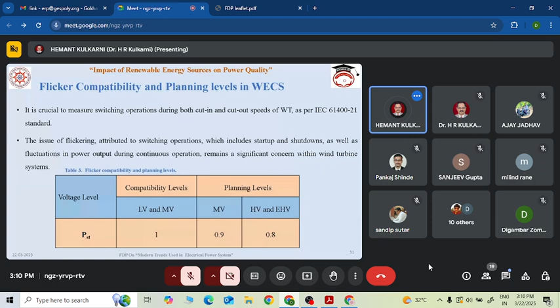Now, how to measure this flicker? Flicker means, again, the change in voltage fluctuation. So how to measure it? There are also IEEE standards or international standards. According to IEC 61000-4-15 or IEEE 1453-2022, a flicker meter model is developed to calculate the short-term flicker severity index, which is called PST. Okay, short-term flicker severity index, and the flicker meter architecture, which is described by the standard.